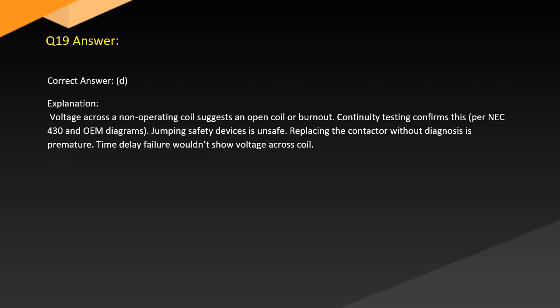Answer. Correct answer, D. Explanation. Voltage across a non-operating coil suggests an open coil or burnout. Continuity testing confirms this per NEC 430 and OEM diagrams. Jumping safety devices is unsafe. Replacing the contactor without diagnosis is premature. Time delay failure wouldn't show voltage across the coil.